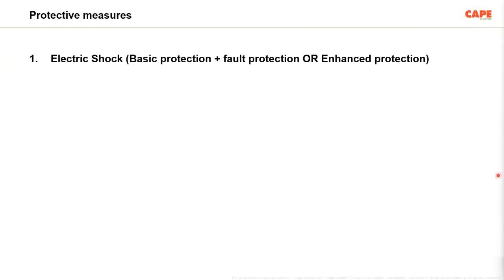For an electrical installation, the protective measures required are categorized into 4: electric shock protection, protection against thermal effect, protection against overcurrent, protection against over voltage. Basically, protection against electric shock is to ensure that people and animals are not getting shock. This is basically achieved by 2 protective measures called basic protection and fault protection. This also can be done by an enhanced protective measure.